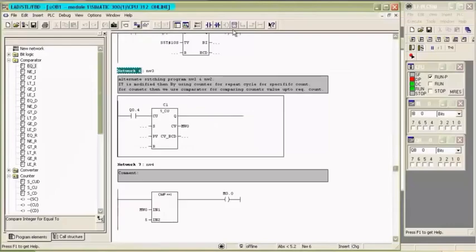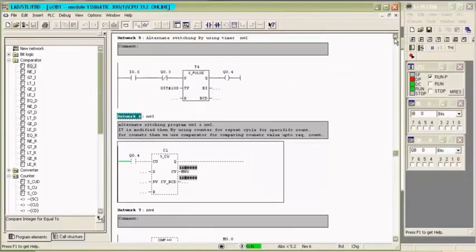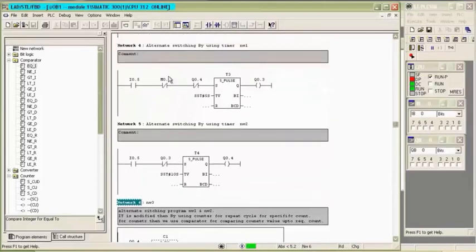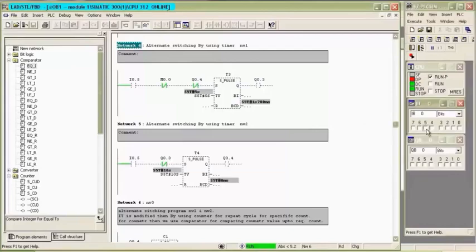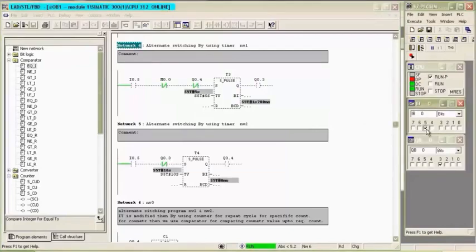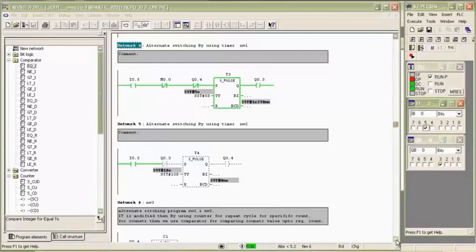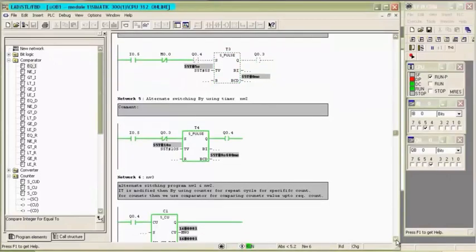Now we run the program. When program goes into run mode, switch on the input I0.5. After that, first pulse timer gets on for 5 seconds. Then second pulse timer will start for 10 seconds.